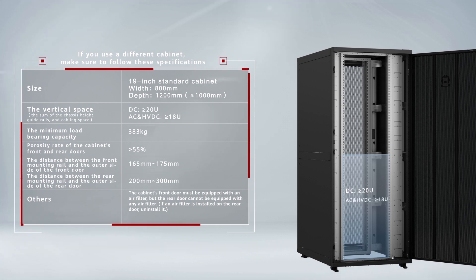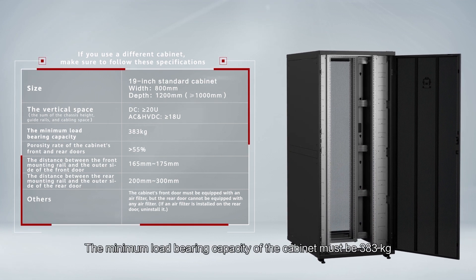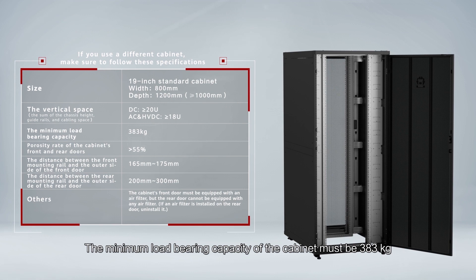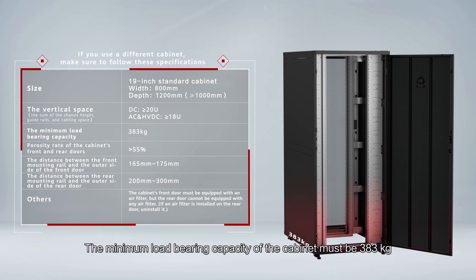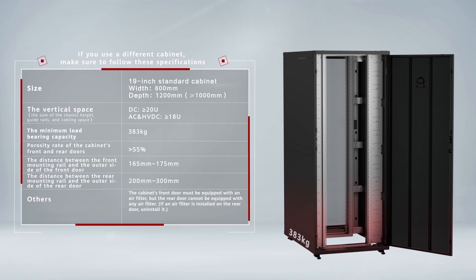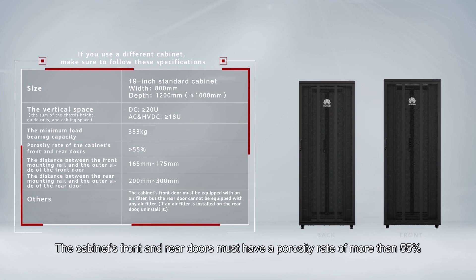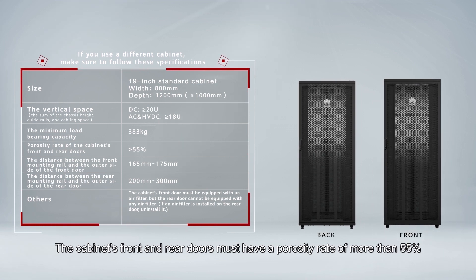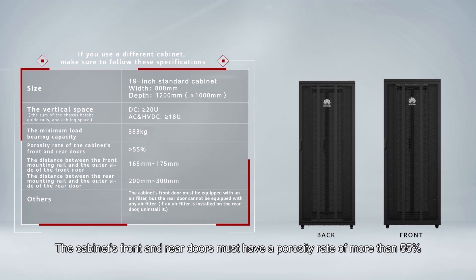The minimum load-bearing capacity is 383 kilograms. The cabinet's front and rear doors must have a porosity rate of more than 55 percent.